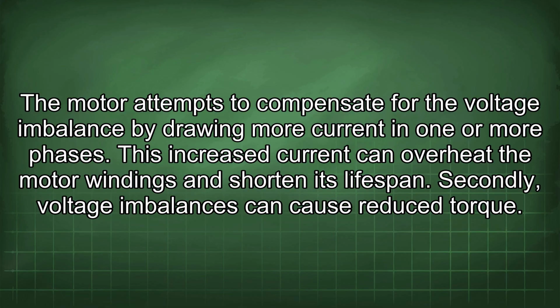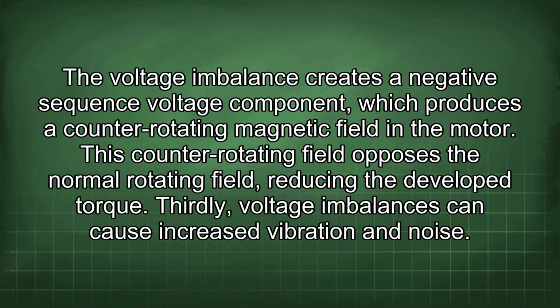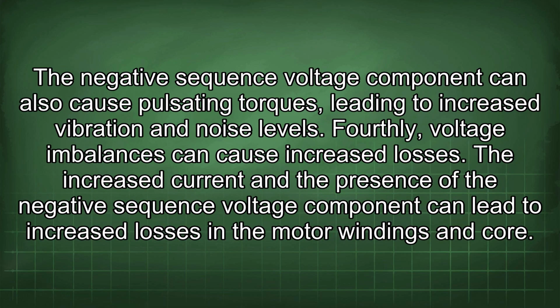Secondly, voltage imbalances can cause reduced torque. The voltage imbalance creates a negative sequence voltage component, which produces a counter-rotating magnetic field in the motor. This counter-rotating field opposes the normal rotating field, reducing the developed torque. Thirdly, voltage imbalances can cause increased vibration and noise. The negative sequence voltage component can also cause pulsating torques, leading to increased vibration and noise levels.